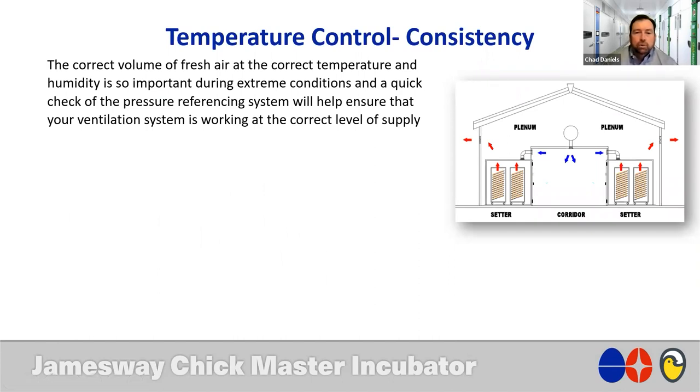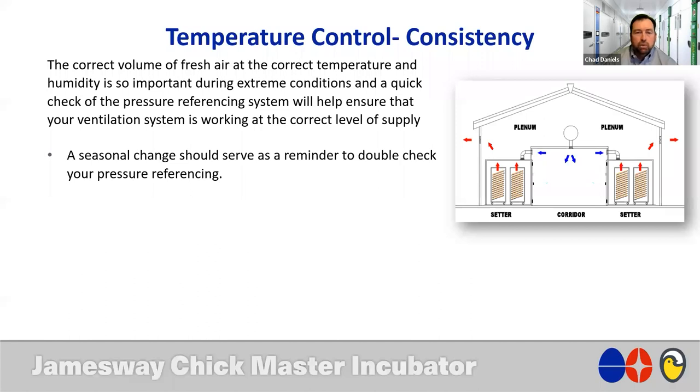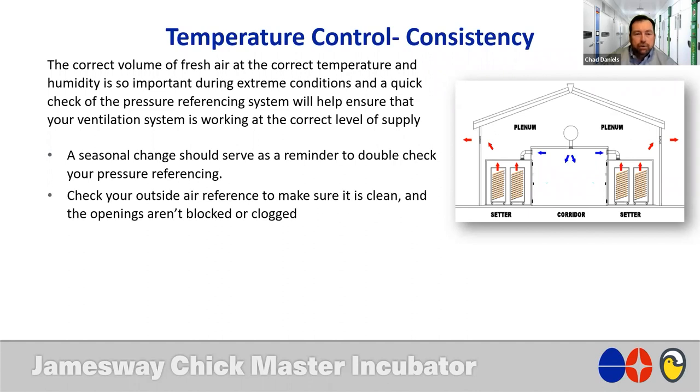Also, when we look at these seasonal changes, it reminds me to always try to tell people to do a quick check of your pressure referencing system, just to ensure that it is calibrated and is operating properly. If that system's not working, again, the room is going to try to provide more fresh air than necessary and giving us some problems. So a seasonal change should serve as that reminder.